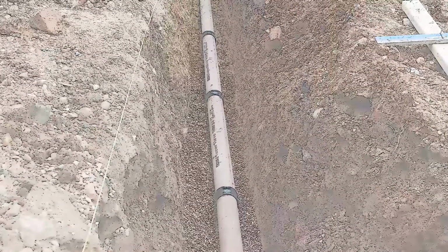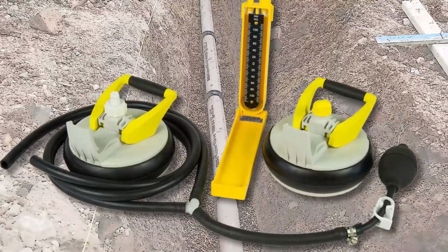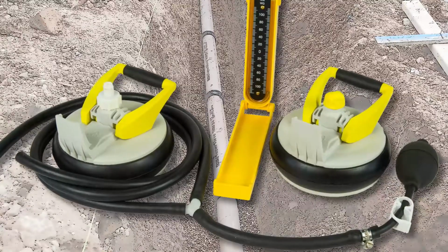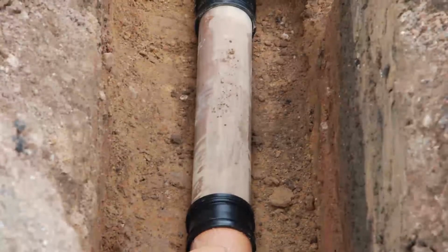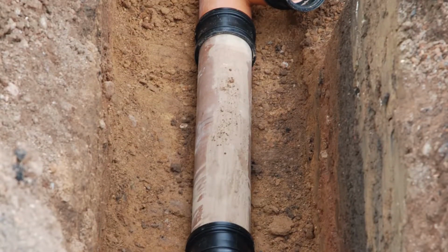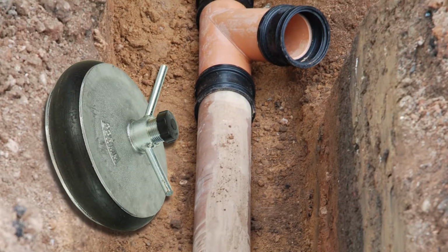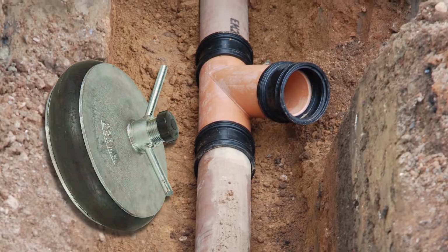Having excluded the environmental conditions or taken them into consideration, you should then move on to checking the testing equipment more closely. Here are a few suggested things to check depending on the type of failure experienced. Check for major faults and even basic oversights, like not stoppering off all branch connections and forgetting to put in or tighten the stopper or fit the end cap at the other end of the pipeline.